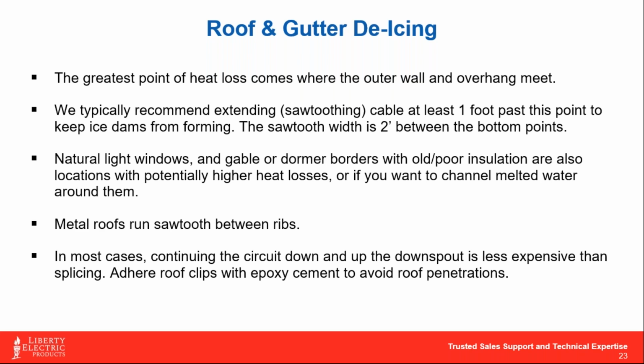If you try to hem it in closer than 2 feet, you're going to use a lot more cable to melt that roof off. So unless you're in a very high snowfall area or someplace where you have to keep it off a particular area, 2 feet is the magic number, that's the right number. And we want to go up the roof, vertically, at least 1 foot past where the outer wall and the overhang meet. That's how we determine the distance on those triangular points.